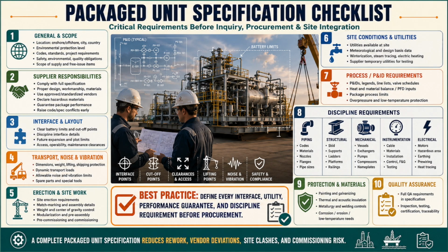State applicable site labor agreements, contractual site conditions, and restrictions. Where site assembly is required, define match marking, flange alignment, bolt tensioning requirements, earthing continuity across flange joints, and reassembly procedures. For offshore and seismic applications, weight and center of gravity are critical design inputs. Require a weight control procedure, regular weight reports, and defined maximum acceleration loads. An inaccurate center of gravity can compromise lifting design, module integration, and structural safety.